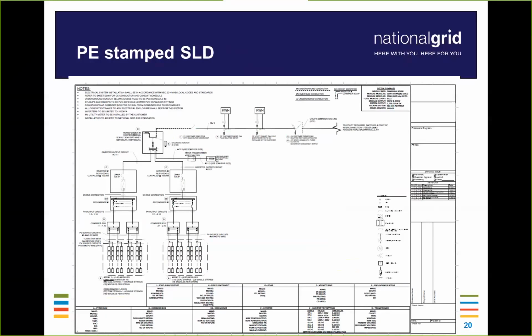Now, if you need help deciding what a symbol should look like to represent a specific device, such as a switch, a hook stick switch, a gang-operated switch, fuse holder, transformer, whatever that device may be, we did take a lot of time and effort to provide a general symbology list within our ESB 756 series, and there is symbology in the 753 and 50 series as well. So if you were to take a look at those documents, the symbology that we added there was in an effort to help guide choices when it comes to creating your own symbology for your drawings. So there are certain items that should generally look similar, if you were to pick up one set of drawings from one consultant and another. So that's to guide and help, and it's very important to have that symbology.